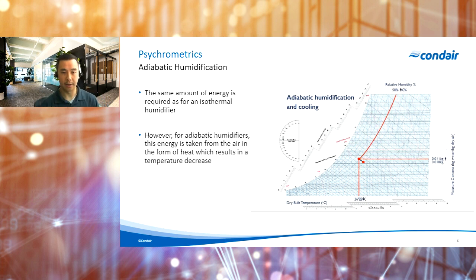Now, the caveat here is really in order to maximize that cooling effect, we want to evaporate as much water as possible. So in reality, what that means is if we're trying to maximize cooling, we could potentially be looking at humidity levels in the range of 80+%. Now, there are ways to take advantage of that adiabatic cooling effect without adding moisture directly to the supply airstream, and we'll touch on that later on.